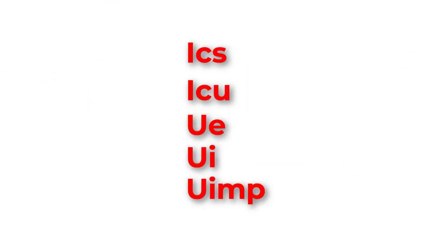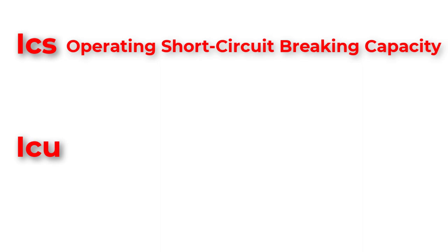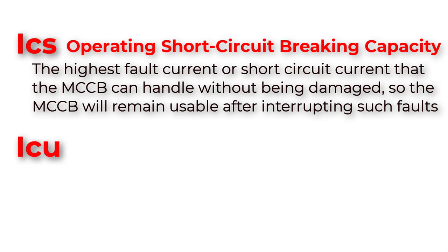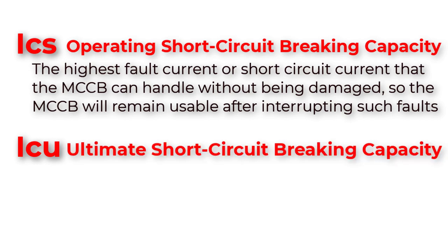Let's start with ICS and ICU. The operating short circuit breaking capacity (ICS) is the highest fault current or short circuit current that the MCCB can handle by tripping without being damaged, so the molded-case circuit breaker will remain usable after interrupting such faults.